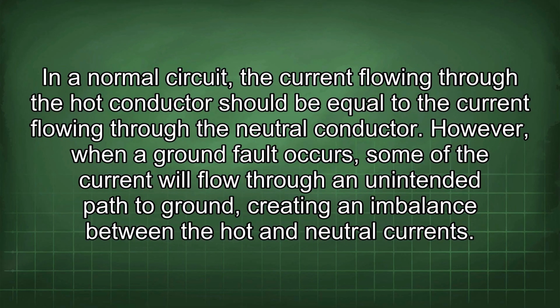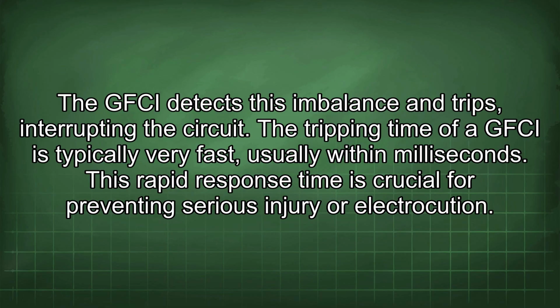In a normal circuit, the current flowing through the hot conductor should be equal to the current flowing through the neutral conductor. However, when a ground fault occurs, some of the current will flow through an unintended path to ground, creating an imbalance between the hot and neutral currents. The GFCI detects this imbalance and trips, interrupting the circuit.